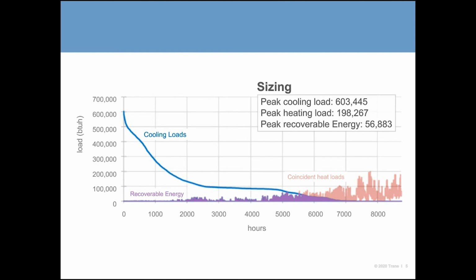What you see here is an 8760 profile sorted by cooling load, biggest cooling load first all the way to no cooling load, with coincident heating loads overlaid. This gives you the purple area here, the recoverable energy hour by hour. That's huge for any high performance or all-electric design—recovering as much heat as you can can be critical and potentially huge for first cost when sizing your equipment. So getting a load profile for both cooling and heating that you trust is a big one.